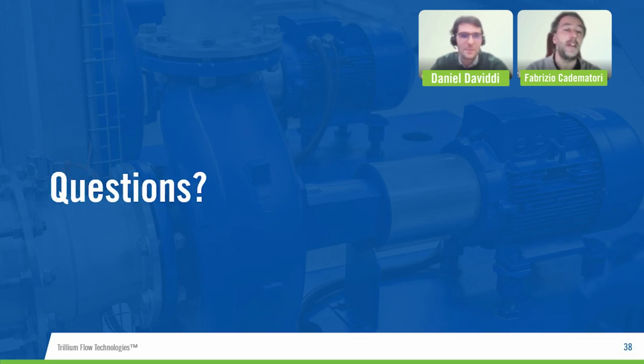Sometimes we have to face this problem, and I must admit that the most common cause is not related to hydraulics, but to resonance with a bearing support. In this case, it is very common that you design your pump and face a problem of high vibration, and you can resolve it by changing the bearing housing support design. But NPSH can also be a problem. But probably if you have a problem of NPSH, you will face a different sort of damage, for example, cavitation and so on. Daniele, do you want to add something? No, I think that the answer is correct.